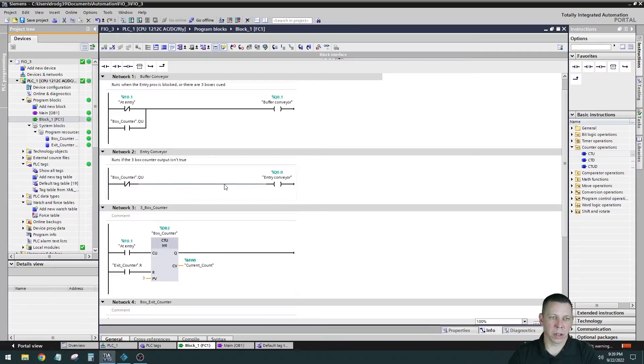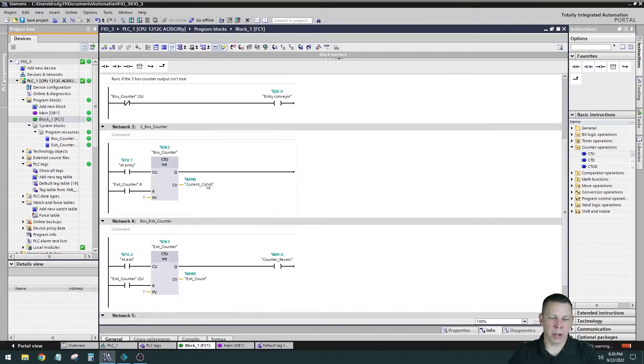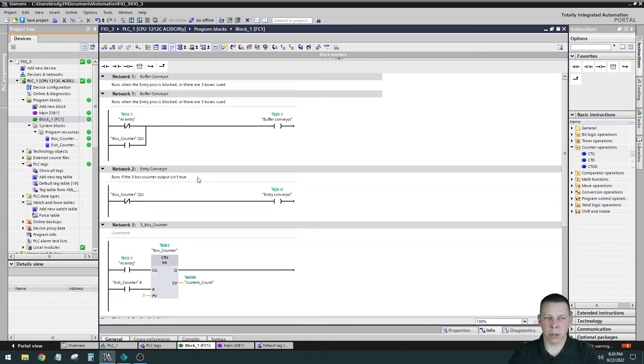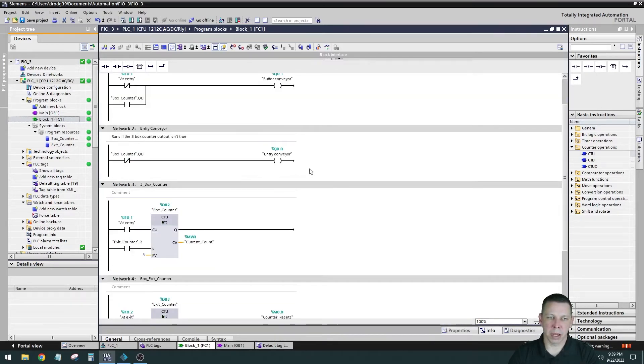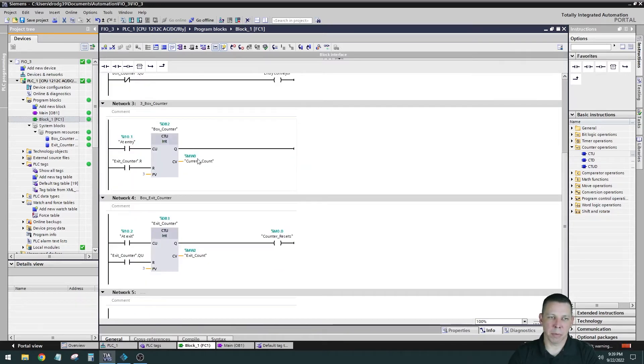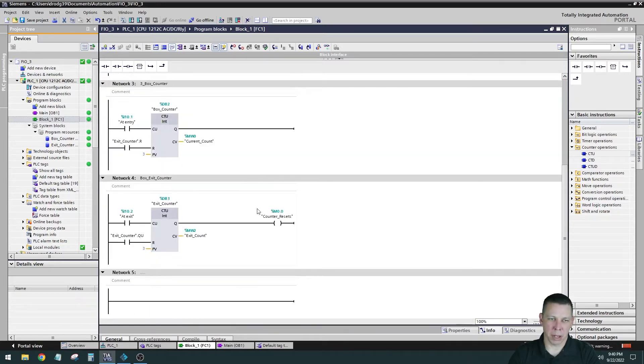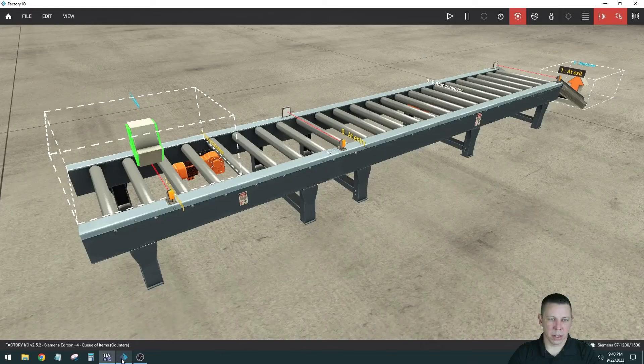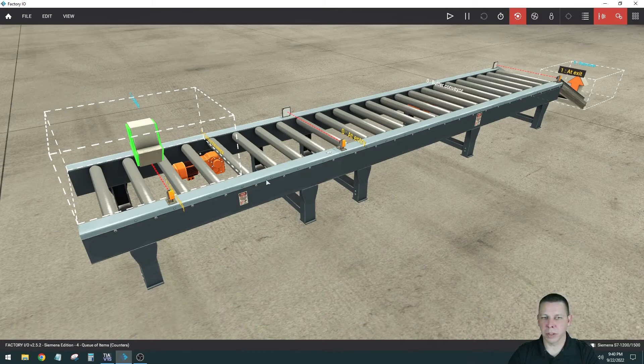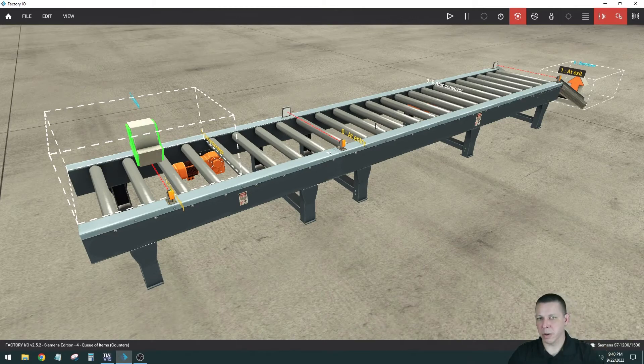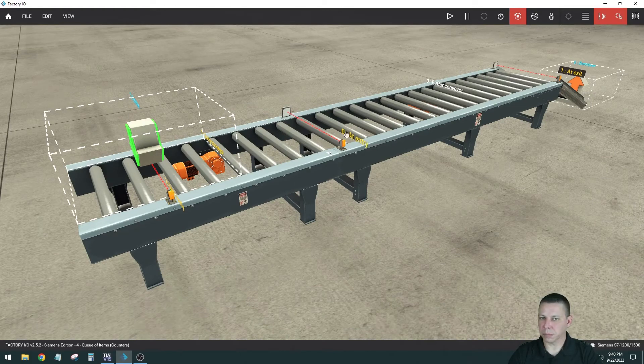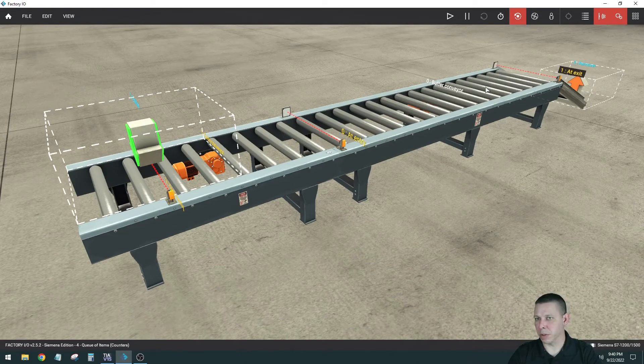So down here is my counter. So I have four rungs. I have my buffer conveyor rung, my entry conveyor rung, and I labeled the networks here and put some comments in. And then I have my three box counter and I have my exit counter. And like I said, there's two conveyors, this conveyor, that conveyor, and it counts three in a row right here. Once it gets three in a row it turns this conveyor off, leaves this one on until it counts three going through this beam. One, two, three.